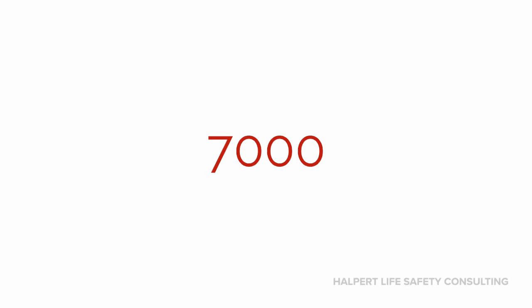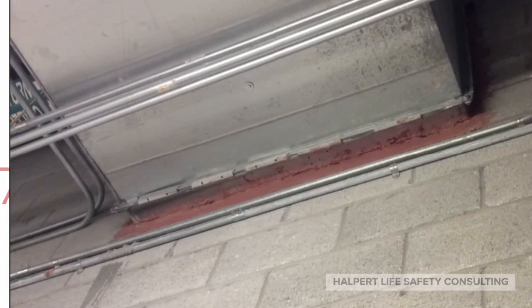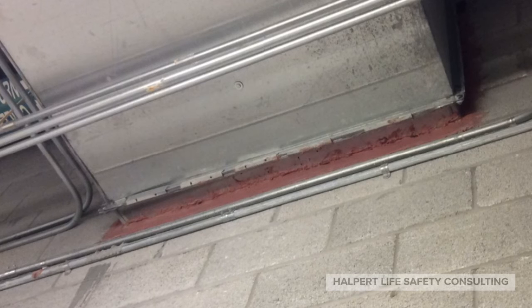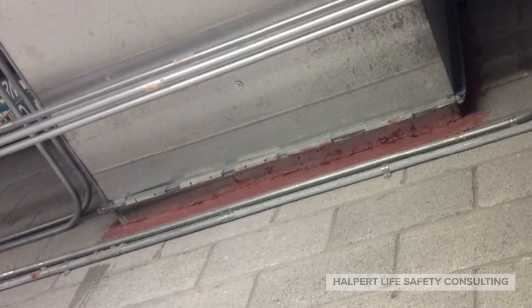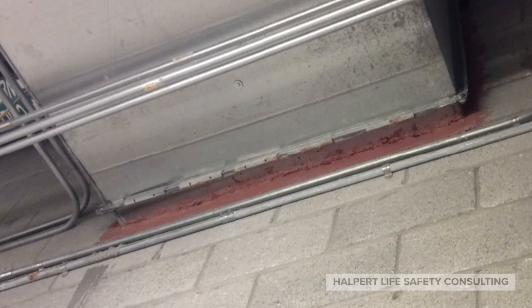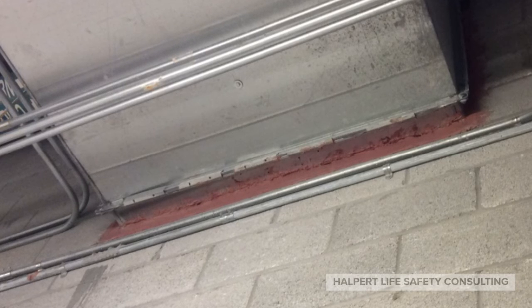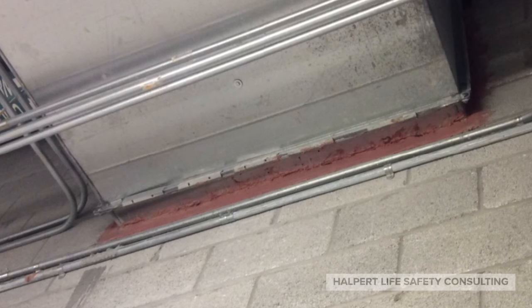If you have a similar condition on your job site with a large duct going through a rated assembly, and it looks just like this does, and you think that the Firestop is done, I'm sorry, you have a problem. Generally, when bare ducts are over 24 inches, there's one more thing that you must do before the Firestop installation is complete. If you don't know, please go back through our archives, and there's a 4 or 5 part series dedicated just to this topic. Alternately, you can call us, and we can explain the issue and how to fix it.